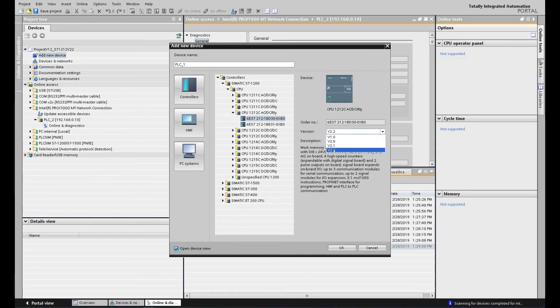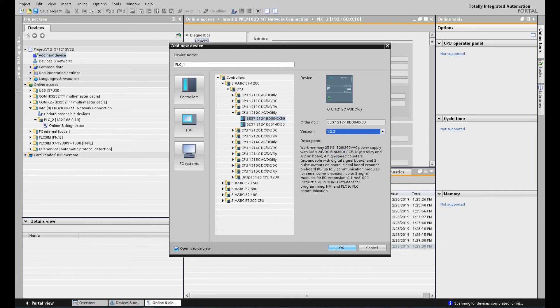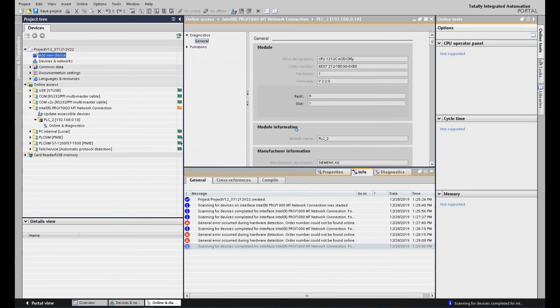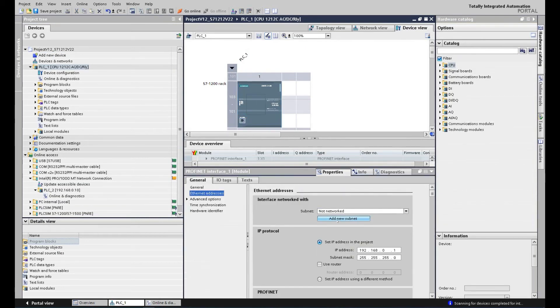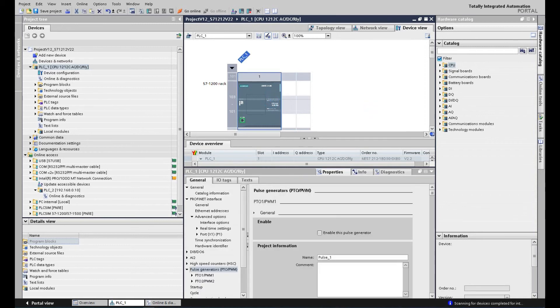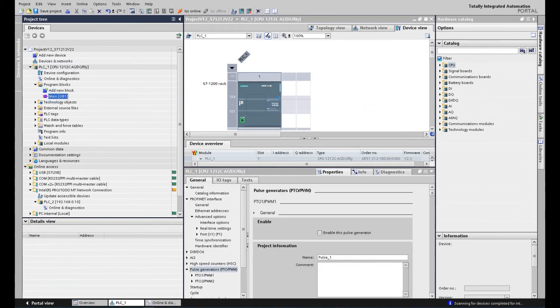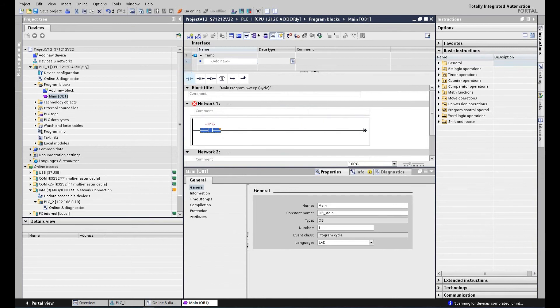The TIA Portal from version 13, that only configured from version 2.2. Some old version controller, the version 13 can no longer configure that. So the TIA Portal version 12 is still valuable to keep in operating system. So let's select 2.2 and click OK. And let's set up the IP address of this controller. We set 192.168.0.10. And let's set up a very simple logic. Let's try to download this simple logic and try to test the communication.